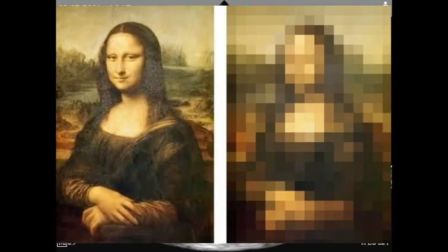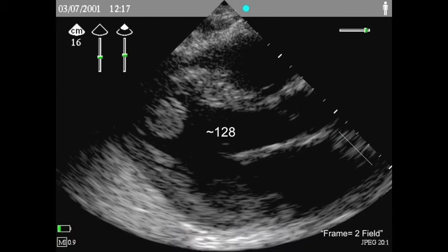to create an image. Now, of course, it would be great to have an infinite amount of crystals, but of course the processing time and the ability to await the return of the ultrasound from the far field limits how many you can have in a moving target like the heart. And this has to do with what we call frame rate, waiting for the ultrasound to come back through each of those crystals in order to produce an image that is updated.